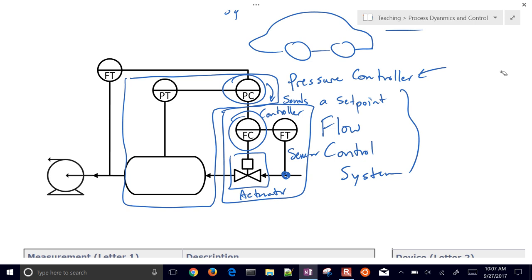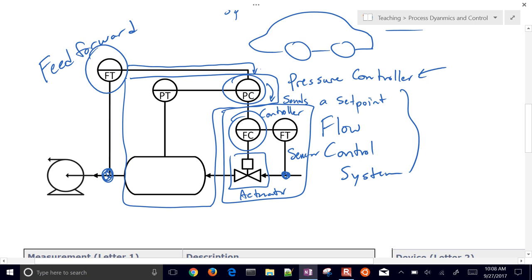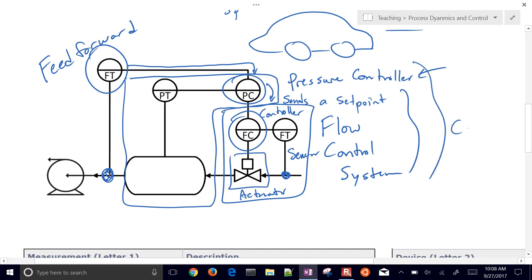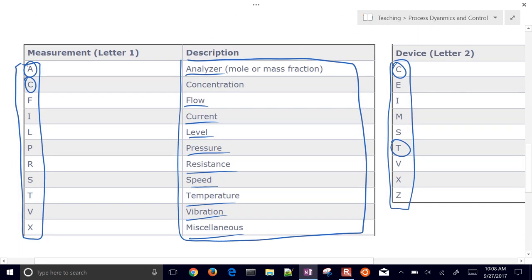We can also have feed-forward elements. These measure disturbances affecting the system that we're not directly controlling, allowing us to reject the disturbance before it causes a deviation from our setpoint. For example, a feed-forward element measures the flow out of the tank and sends a signal to the pressure controller, saying there will be a change in pressure soon so adjustments can be made now to avoid deviating from the desired pressure setpoint.